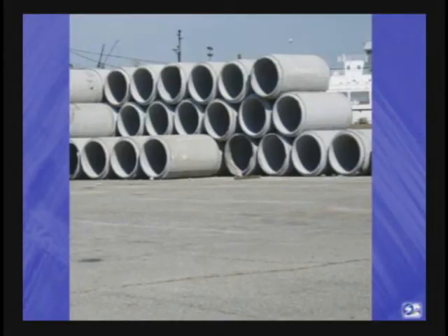The extent of shedding asbestos from those pipes is dependent on the characteristics of the pipe, whether it's coated or not, and the aggressiveness of the transported water, which is calculated based on the product of the water's pH, its hardness, and its total alkalinity. It was determined that at least 66.5%, or 2 out of 3, of the US water systems have properties that can erode fibers from asbestos cement pipe.